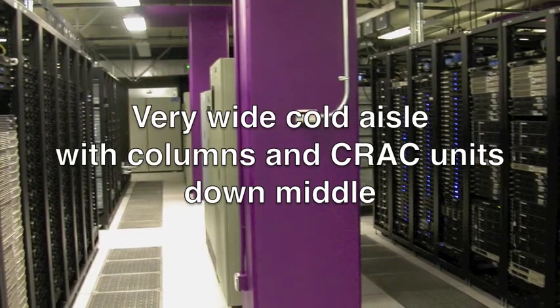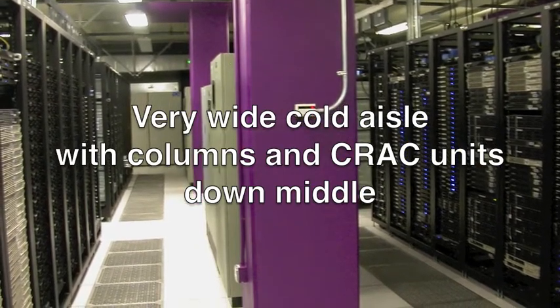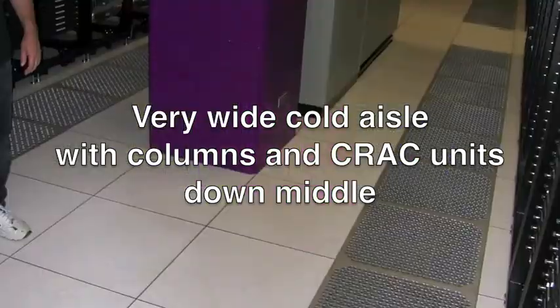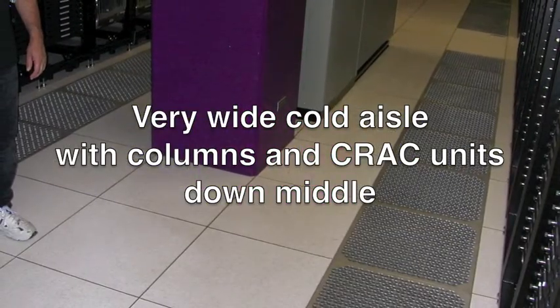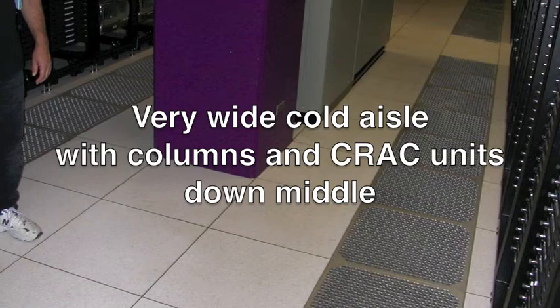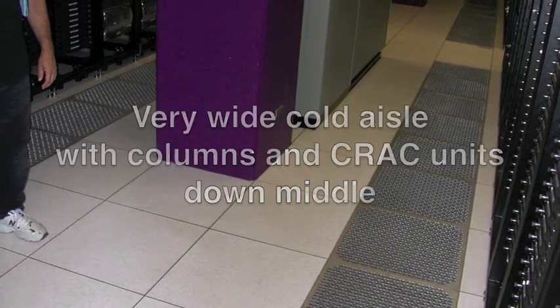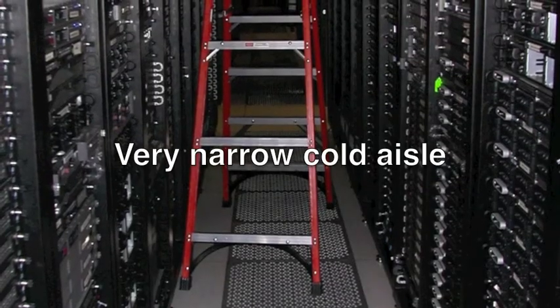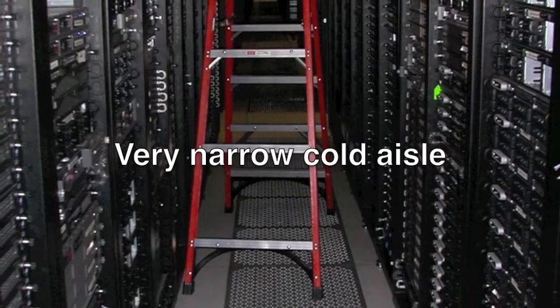Here is a particularly difficult area to contain because it's a 10-12 foot aisle, plus there are columns and air conditioners in the middle of the aisle, so that one's pretty complex. And opposite of the wide aisle is sometimes you get very narrow aisles, and those can actually be a bit easier to contain.